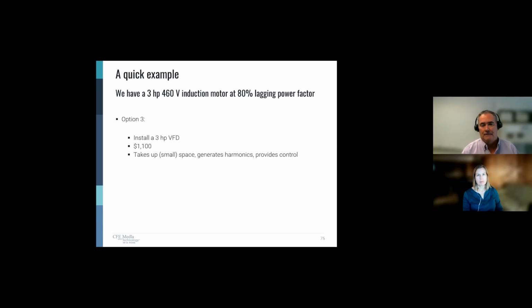The third option would be to install a 3 horsepower VFD. About $1,100. Again, I'm not taking into account a bypass or a disconnect or wiring and so forth. It takes up a little bit of space. It does generate some harmonics, but it now provides us control. So maybe where we ran our fan full speed, maybe now we could run it at 90% speed and gain some advantages there. All right, I'm not going to factor that into the math we're about to do here in a minute, but it's a possibility. As we do each of these analyses, we have to figure out what's valuable and what's not.